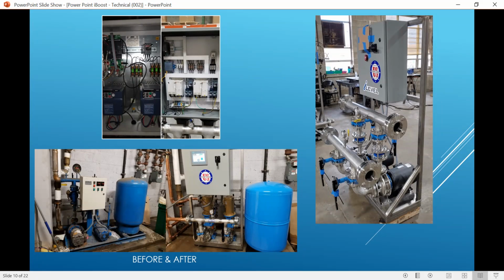Probably the most common benefit is that the pumps don't run as often. If you have small pressure drops either on the weekend or during the evening, the pump doesn't have to kick on and start. You can use the existing supply in the tank, and it gives you a longer life and a little bit more ease of use in terms of how often the pump system turns on and off. So we like to use them.